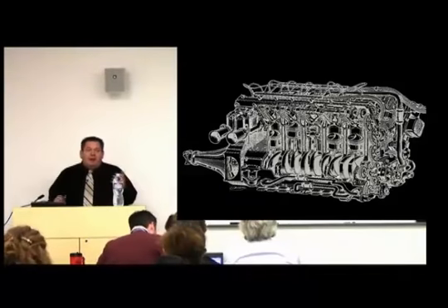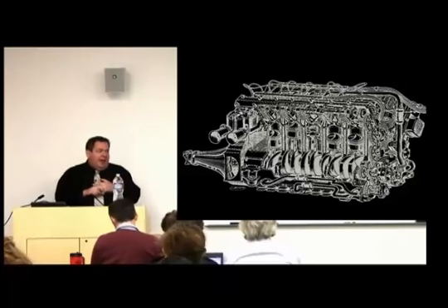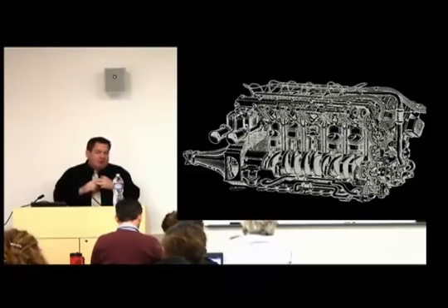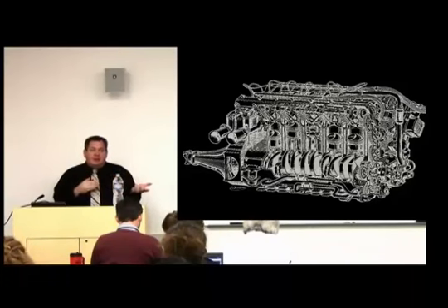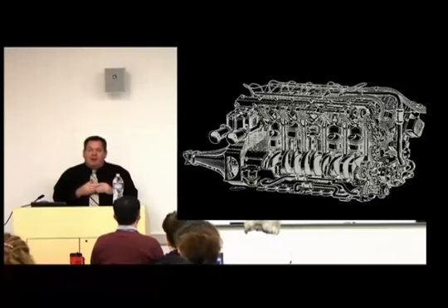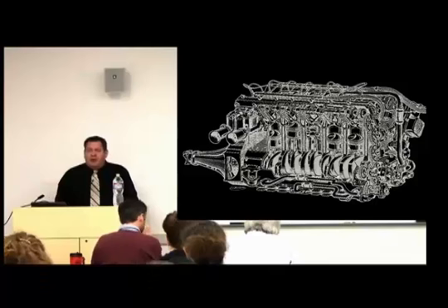All right, so that was applicability. Who and what does this rule apply to? All stationary engines of all sizes at major sources, and then at area sources, which is all sources that are not major sources, so we're pretty much saying all sources, new, reconstructed, and existing sources. So existing engines greater than 500 horsepower at major sources before December 19th of 2002, existing engines that are equal to or less than 500 horsepower, or any engine at an area source. And then new or reconstructed engines are any engines that are not existing engines.